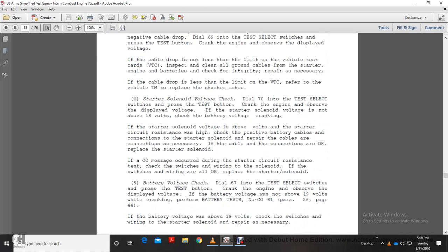Starter solenoid voltage check. Dial 70 on the test select switch and press the test button, ensuring that the engine cranks, and observe the display voltage of the starter solenoid voltage, which should be above 18 volts. If the starter solenoid voltage is below the battery voltage while cranking, circuit resistance is high. Check the battery cable connection at the starter solenoid; repair the cables or connection as necessary. If the cable connections are good, replace the starter solenoid. If a message occurs during the starter circuit resistance test, check the switches and wiring to the solenoid. If the switch wirings are all okay, replace the starter solenoid.